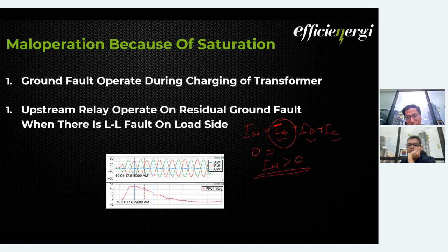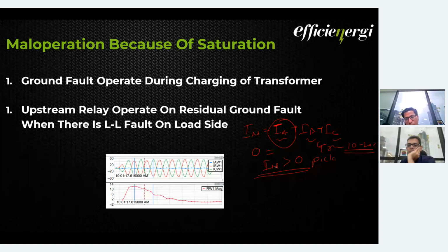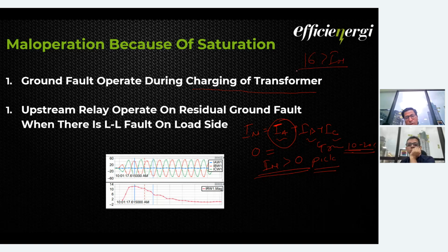And if it is in the range of pickup, because for a ground fault, generally the pickup is in percentage, in the range of 10 to 20%. It is very low. So it is possible that this IN can go more than 20% or 10%, and the relay picks up on a ground fault. The same case happens with the charging of the transformer. If you know the charging of the transformer, sometimes the current goes more than 16 into rated current, 16 into IN. So in that case, in the first few cycles, one of the CTs gets saturated, then this equation comes into picture, and because of that, IN is greater than 0, and it picks up on the ground fault, even though there is no ground fault.